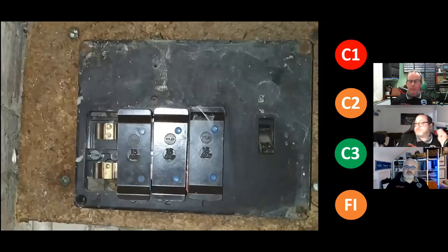Hey Dave, next one. Now, this is a common sight. Yeah, this is a Wylex rewirable fuse box. Several things wrong with this, most obvious being, of course, on the left side there, those big chunks of brass. I'm going to assume this is readily accessible? Yep, it is. Okay, this is shared, and you could just walk in there, and there it is on the wall at about eye level. So that's one. C1? Yep, C1.